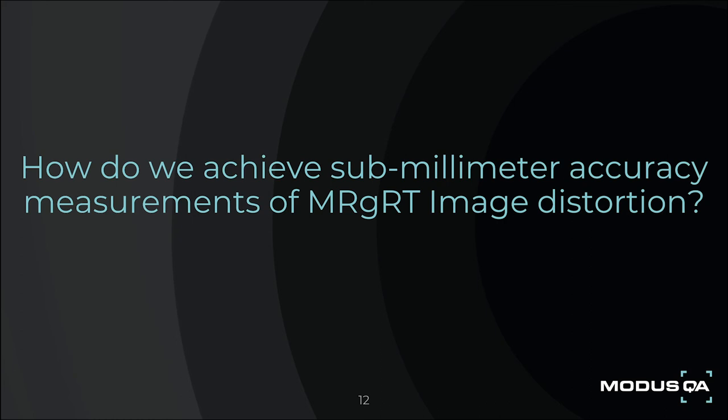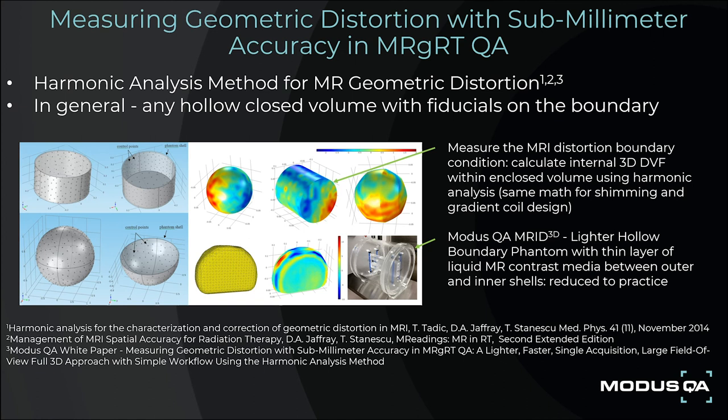How do we achieve sub-millimeter accuracy measurements of MRGRT image distortion? The harmonic analysis method is a fundamental analytical tool for well-defined boundary value problems such as MRI gradient coil design, gradient nonlinearity distortion correction, and B0 shimming. The harmonic analysis method has recently been adapted for sparse and highly efficient sampling and measurement of inherent MRI B0 and gradient nonlinearity system distortion. In general, any hollow closed volume with boundary fiducials can be used. The measured boundary condition on an enclosed hollow volume — a cylinder, for example — if sufficiently sampled, completely defines the conditions within the enclosed volume.